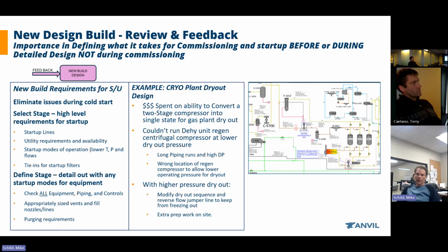Define stage. This is, again, we're getting more into the details at this point. So we're going to be checking all the equipment, the piping, and the controls. There may be different startup modes. There might be low pressure and high pressure interlocks that we're going to have to bypass, in order to be able to come up at lower pressures. Say, like, for example, for this plant, we have to do dry outs at low pressures. Biggest headache I always see is, give us appropriately sized vents and fill lines. I'm trying to fill 7,000 gallons of amine, and I have a 1-inch line, or a 1-inch valve in order to fill it. The other big one is purging requirements.